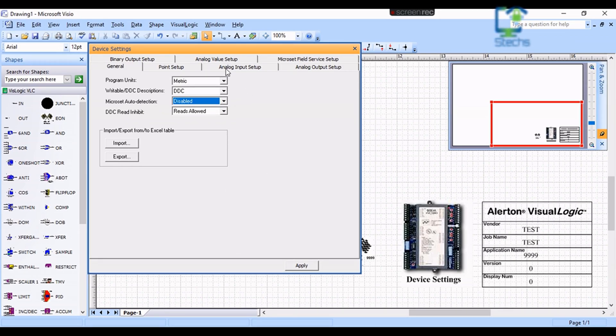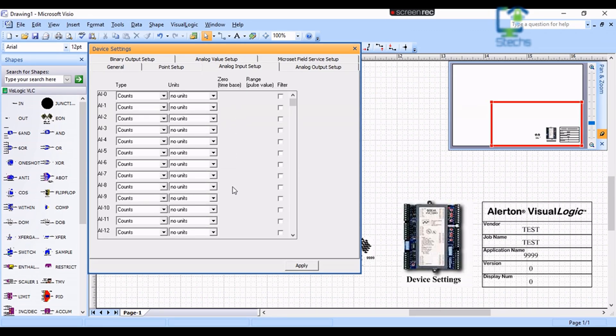On the next page you can see Analog Input Setup. If we have any analog inputs connected to the VLC we can configure that particular input for that device. Analog inputs include temperature sensors, pressure sensors, flow sensors, humidity sensors, CO2 sensors, etc.